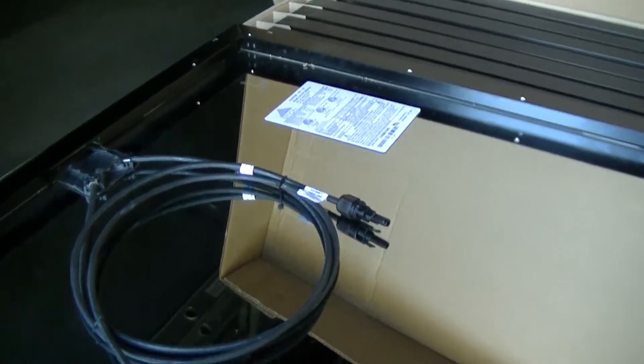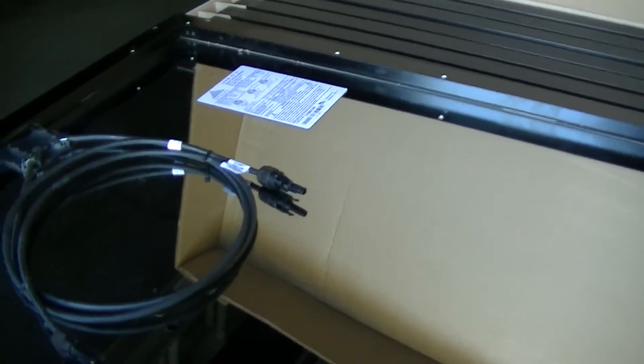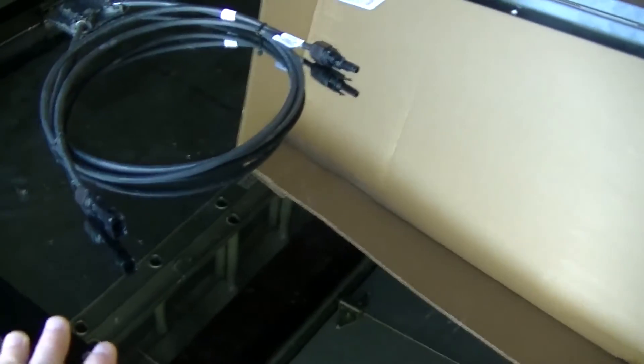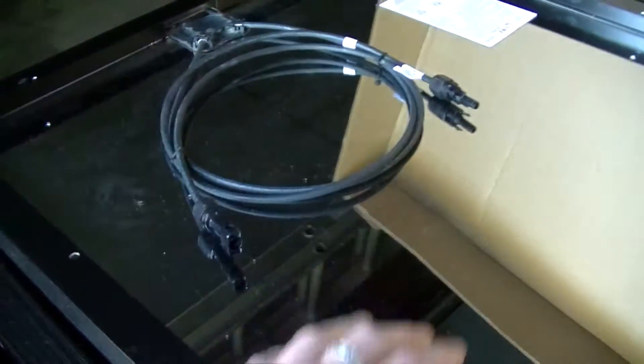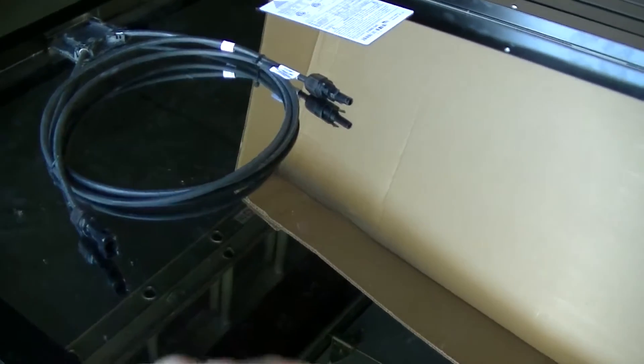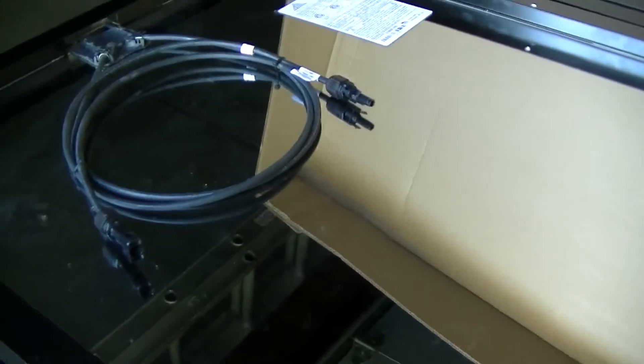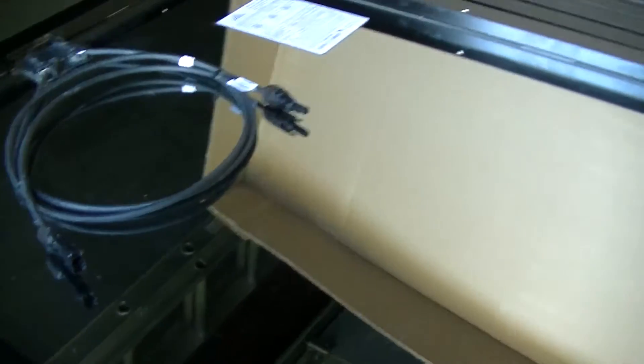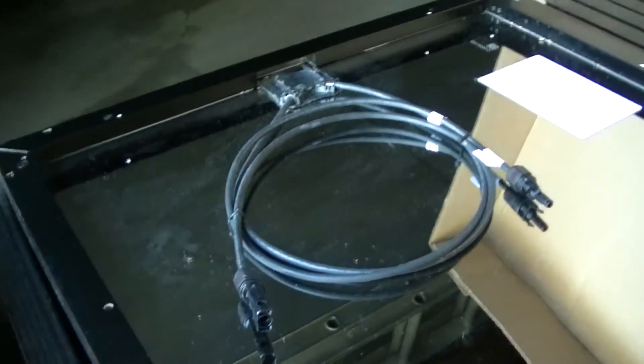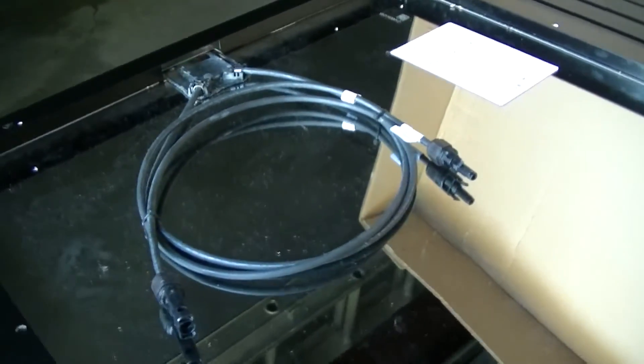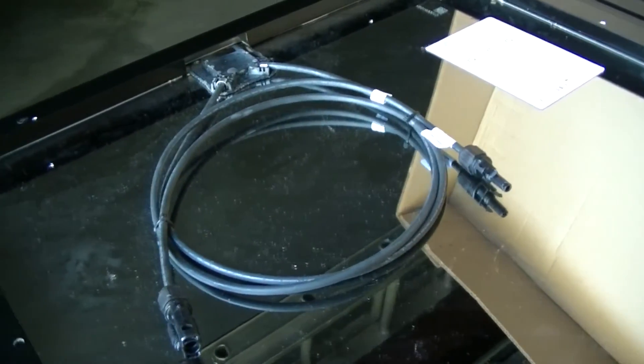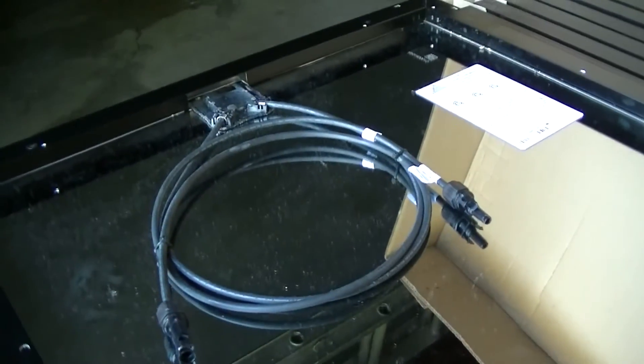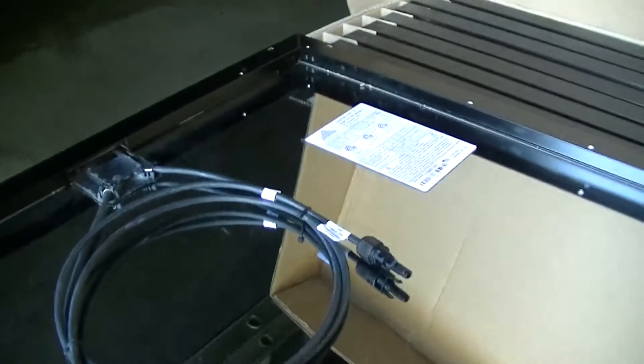So it's a grid tie inverter, but it also has an emergency feature where it has a special outlet that comes off of it separately, that if the grid is down, you can turn that outlet on and it will supply up to 1,500 watts to that outlet. So that's pretty nice. It also comes with a DC disconnect. We are actually going to have to get an AC disconnect also, because our power company requires us to have an AC disconnect on the outside of the house that they can access. So we're going to have to get that too.